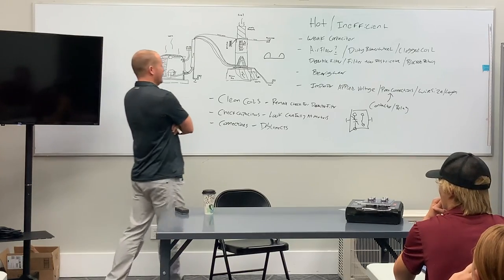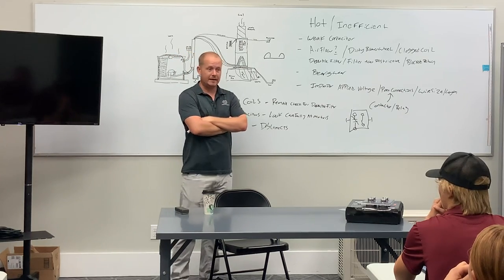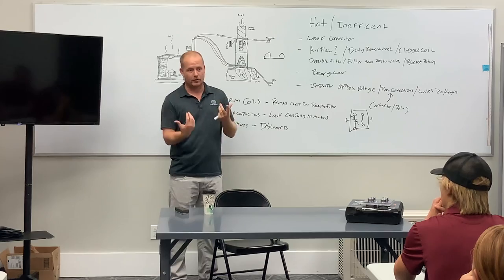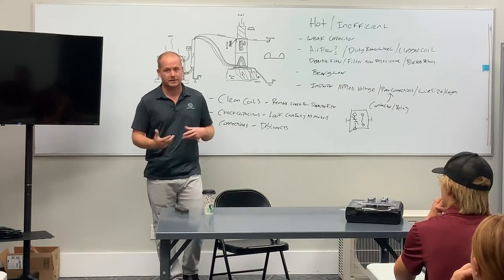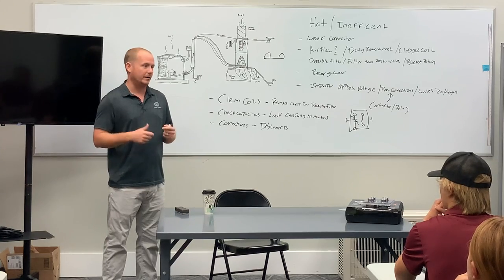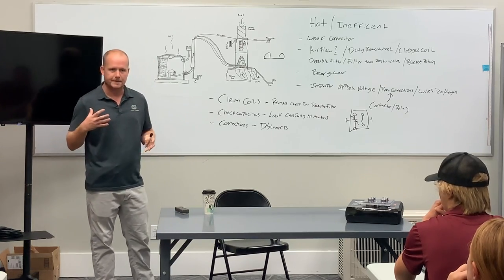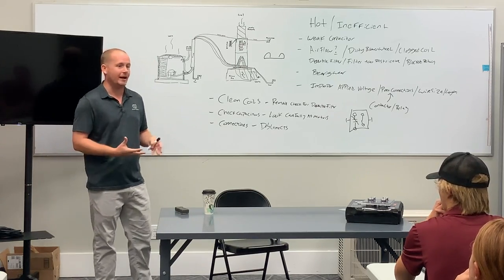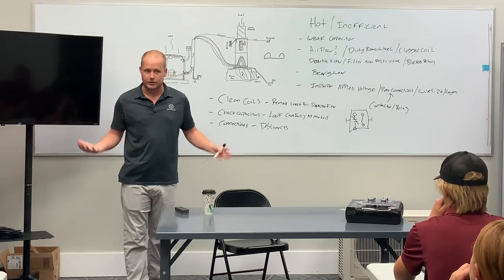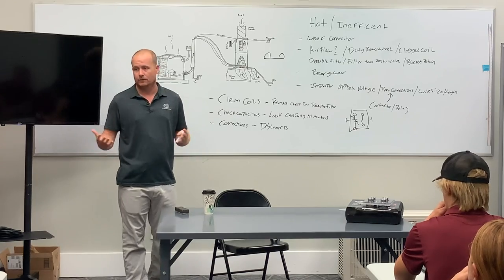So if you've got wires coming in that don't have bushings, or even whips coming out of disconnects that are broken off and water's getting in them, or any of that sort of stuff, you can quote to replace all of that, bundled together with other repairs. These are small things where you can create some added value and add a discount for the customer. So we want to make this a win-win. But let's address the things that need addressing while we're there.